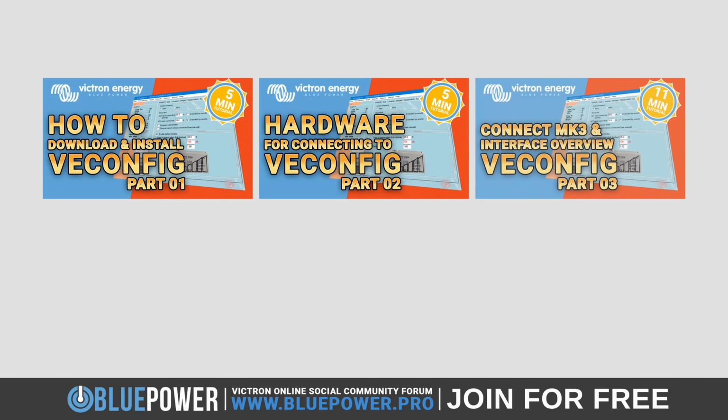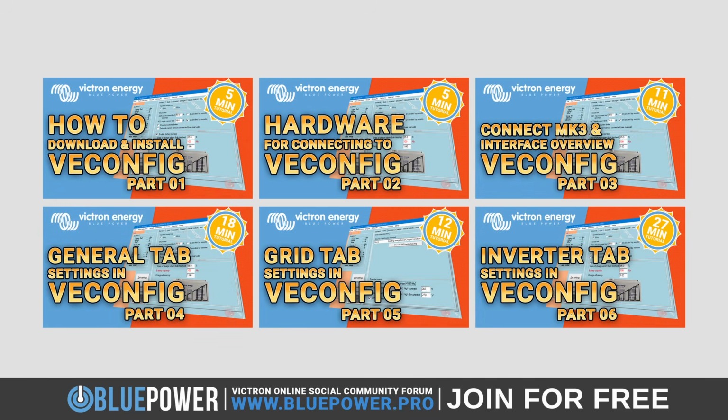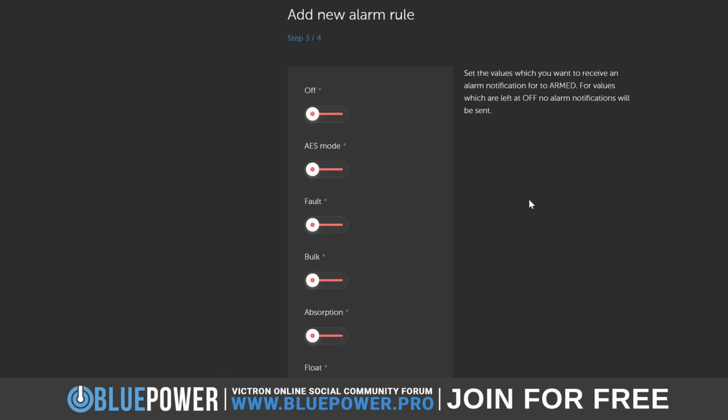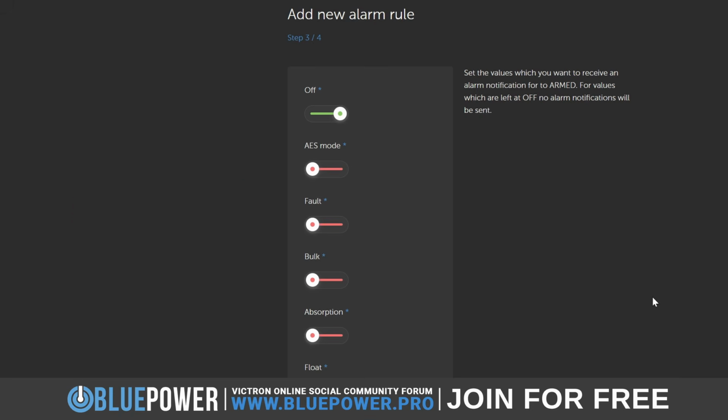If you don't know what a certain setting does, then make sure to check out our in-depth video tutorial series on VE config that explains almost all of these features in detail. For this video though, I am going to only choose the ones that I use in the real world. The first of these is the off state, which will cause VRM to send me an alert should my inverter ever turn off completely. The second one that I use is either the bulk or absorption modes.